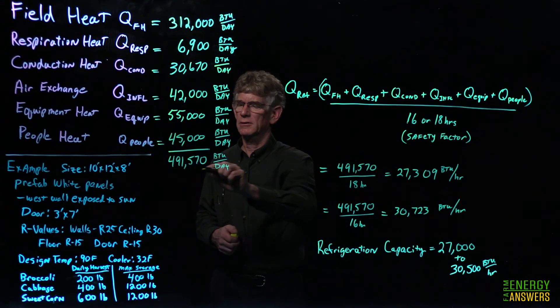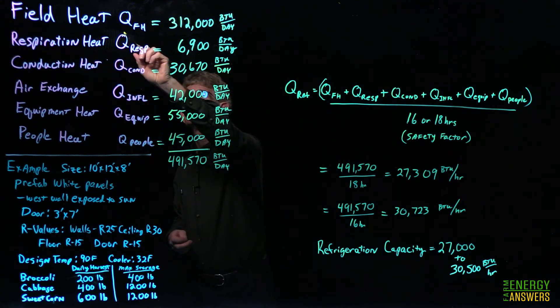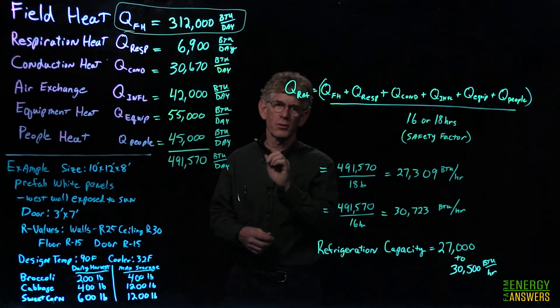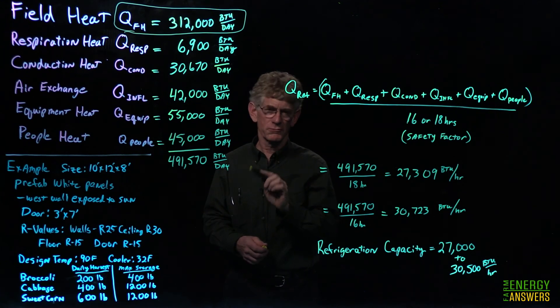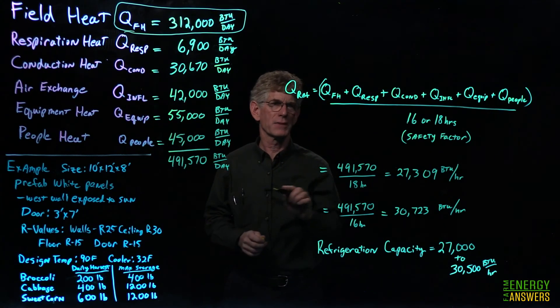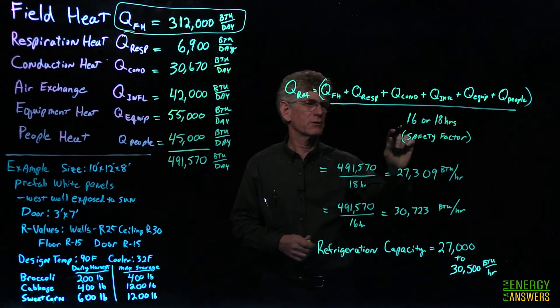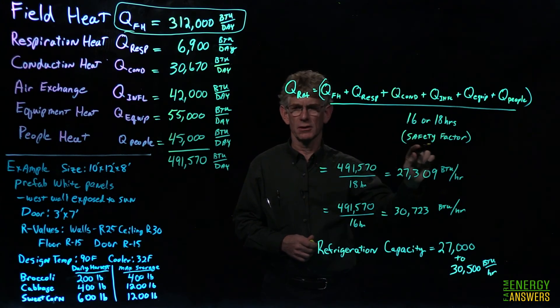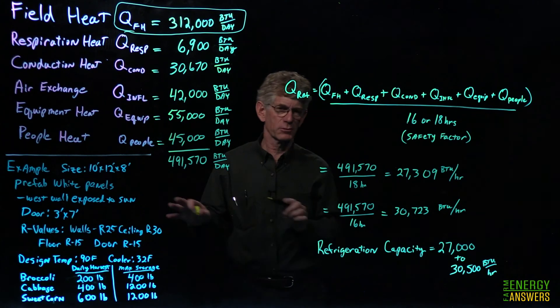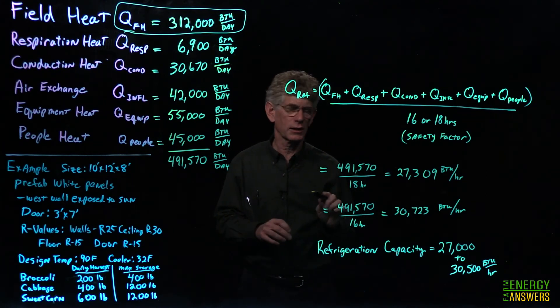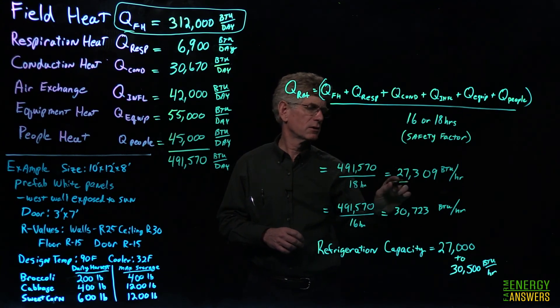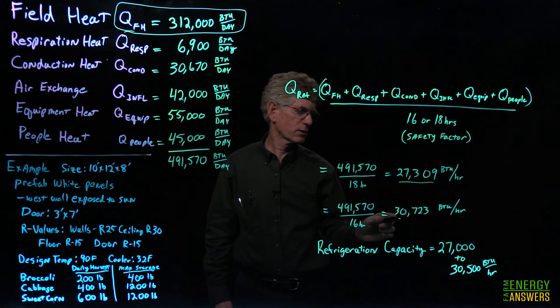For the final summary, we total all components, which comes to approximately 491,000 BTUs per day. Field heat is by far the biggest component and dwarfs everything else — it's the most critical calculation because it most affects refrigeration sizing. If the system isn't large enough, you won't get the product cool fast enough to retain quality. We then divide the total by 16 to 18 hours as a safety factor — we don't want the system running 24 hours a day, because if numbers are slightly off or you put in more produce than planned, you won't cool fast enough.